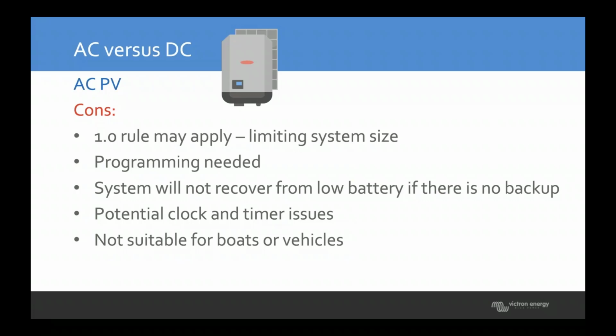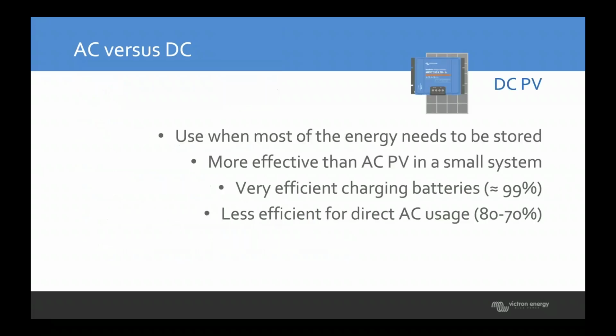It's also not suitable in boats or vehicles. AC PV is potentially more dangerous than a DC PV with lower voltages. And also earthing issues. AC PV requires an earth fault alarm and things like that, and that's more difficult on a boat and vehicle to do safely. So you're better off with DC PV via a Victron MPPT on a moving vehicle.